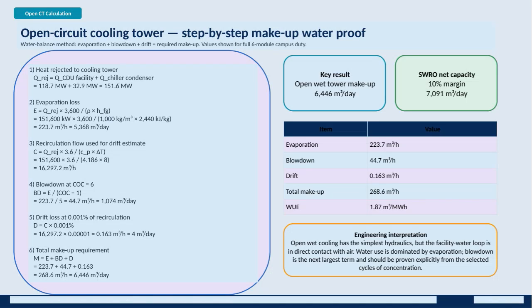The main takeaway from this training is that the type of cooling tower directly influences water exposure, treatment needs, control strategies, physical footprint, and water use efficiency. It's essential to base water-saving estimates on actual evaporation, blowdown, drift, and wet fraction calculations rather than assumptions tied to tower types or names. This ensures proper system design and operational efficiency in the data center cooling process. Here, we walk through the open cooling tower calculation using the water balance method, where the makeup water required equals the sum of evaporation, blowdown, and drift losses.